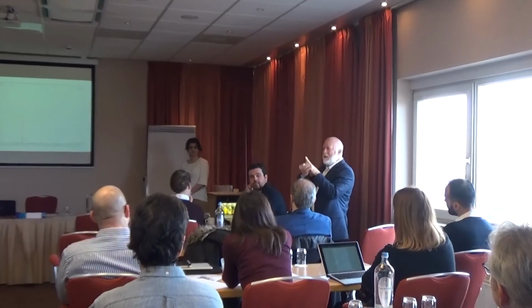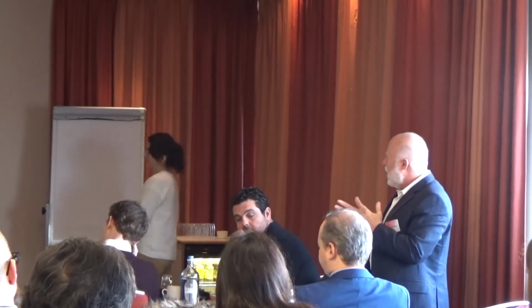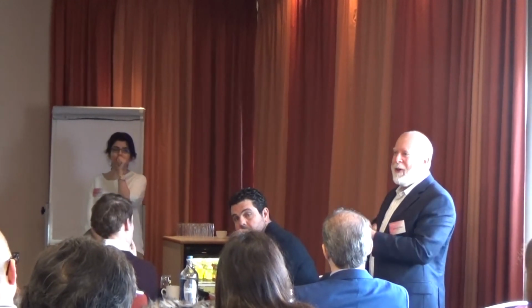Well, I think it's super important to be able to handle other solvents, right? Yeah, if I can answer that one. For the most part, the Echo will transfer the solvents. Generally, what we hadn't optimized for, because it wasn't a requirement previously, was to make all the drops land in the same spot. So they haven't been designed to optimize that, and the work that we need to do is to make sure that not only are they volumetrically accurate, but the placement is correct.